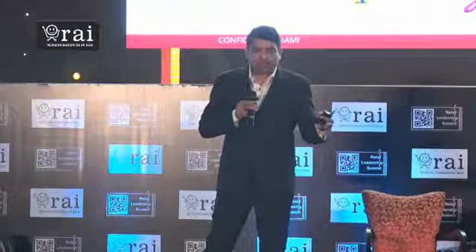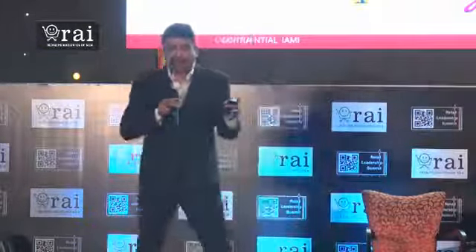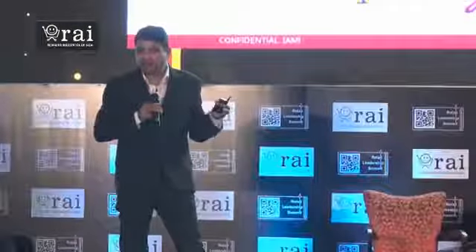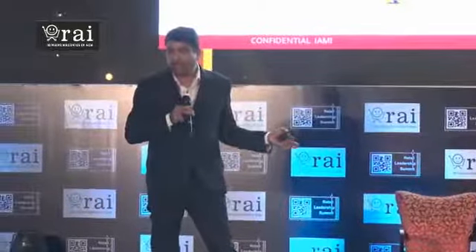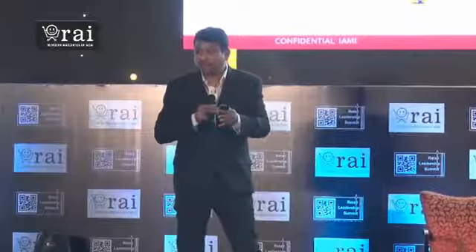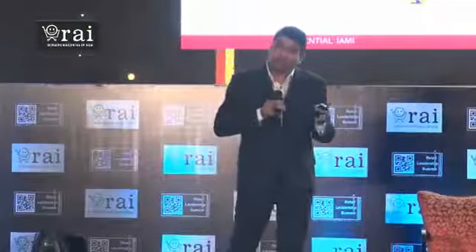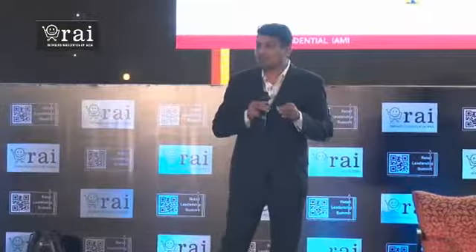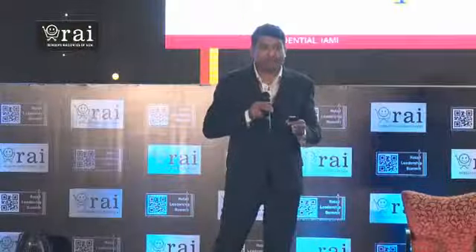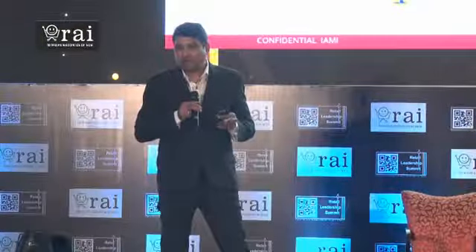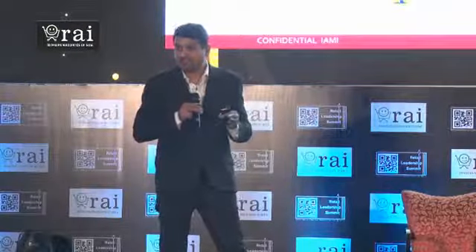In some retail stores, as I explained, we have done audits and surveys where the energy requirement is, say, around 50 kVA, and the sanctioned load is maybe 25 kVA, so you get a straightaway penalty to pay. In other cases, 100 kVA is the load sanctioned by the electricity board, but you are utilizing only 40 to 50 kVA. So you are honestly paying a cost for energy you are not utilizing at all.